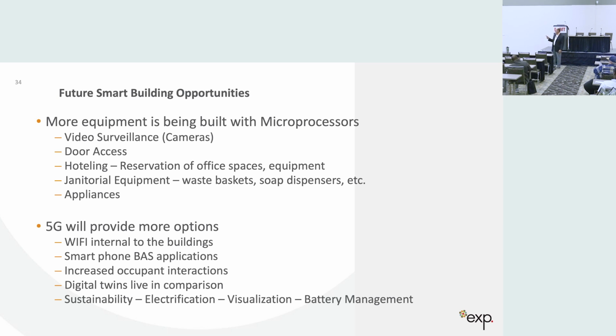We want to make sure we're focused on the occupants, and then digital twins. You have all this data, and you know what the building's supposed to do. You develop a digital twin, there are different definitions of it, but basically you can have a digital twin of your chiller plant or something like that, showing how it should operate. Then you compare that to the actual, and see if there's a difference. If there is, you generate a fault, and that fault tells you, hey, look at your digital twin, maybe something's not set right, maybe a pump's running or a valve isn't open. You want to know that.